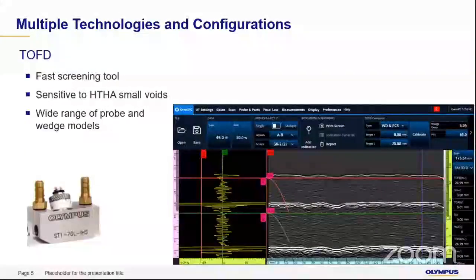We also have a TOFD series of probes for HTHA. Because TOFD is almost the fastest technique, it gives you a faster screening tool and is very sensitive to HTHA for smaller voids. There is a wide range of probes and TOFD wedges available.